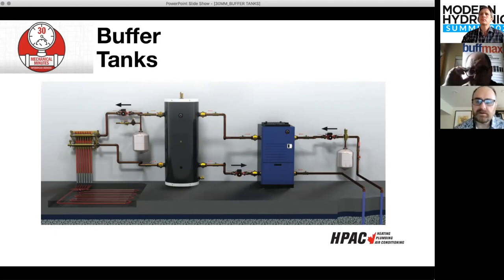Okay. Yeah, the other point I'd like to make there is, it just makes sense. If you've got an appliance, whether it be a boiler or a heat pump or whatever, it's making heat, or it may be cooling in the summertime. It's basically moving energy. Now, the demand on the other side, where we're distributing that heat or the cooling, that varies. On a cold day, even if it's a single zone system, but if multiple zone systems, it amplifies the problem. How much heat or energy you're drawing varies. As it gets colder, you need more heat. As it gets milder, you need less heat. So that demand is changing.